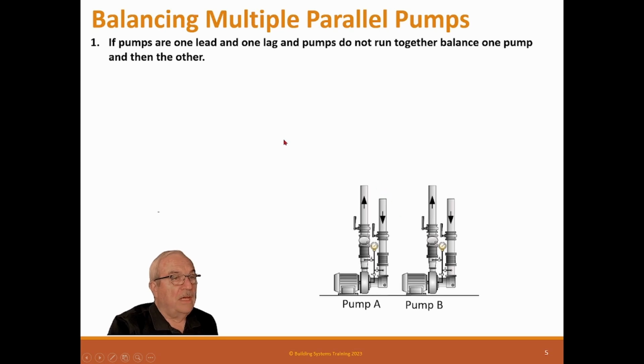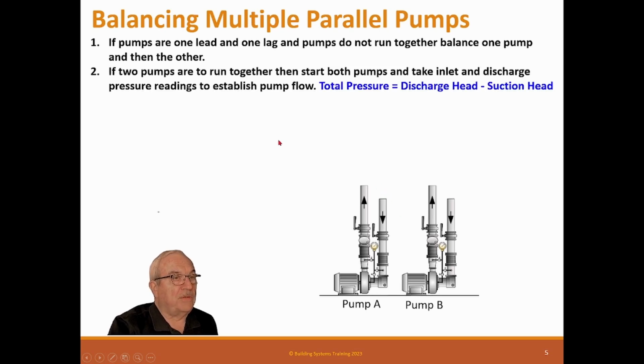That's all you do. However, if you've got staged pumps, where you have two pumps that run together, then start both pumps and take inlet and discharge pressure readings to establish pump flow. When you get both of these running, you take your suction readings, and they'll be the same. You take your discharge readings, and they'll be the same. So now you have the pressure readings of both pumps. Now, why do we do that? Why don't we just balance one pump and then balance the other pump? Because if we're running 50% flow in the system, the pressures will be way, way down, and so it won't be a good connection to the pump. If they're both supposed to run, then you have to put them together to take the readings.